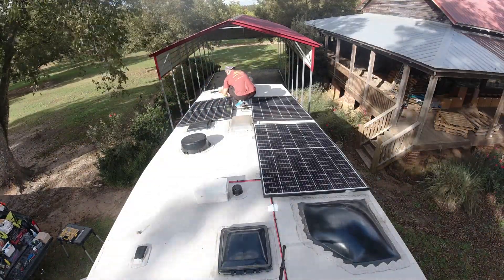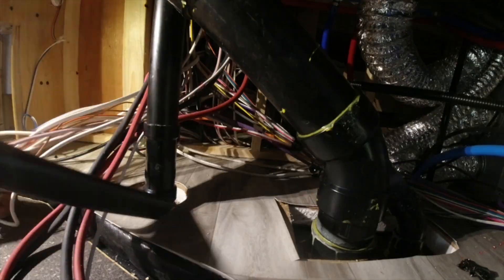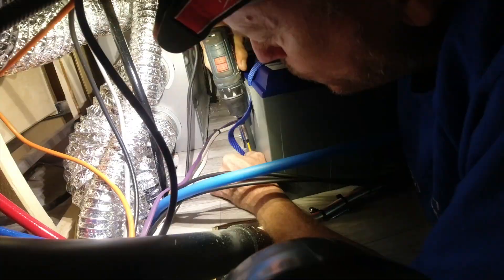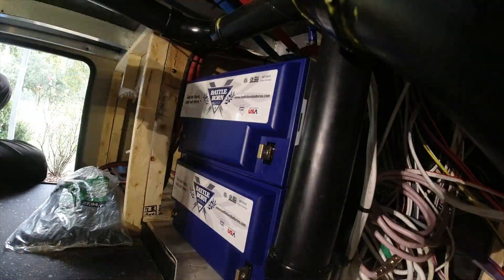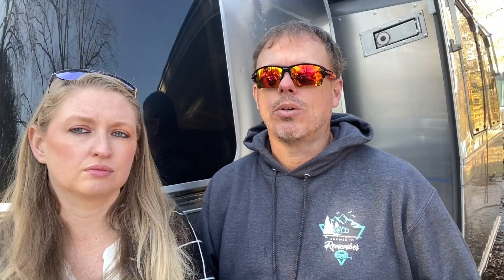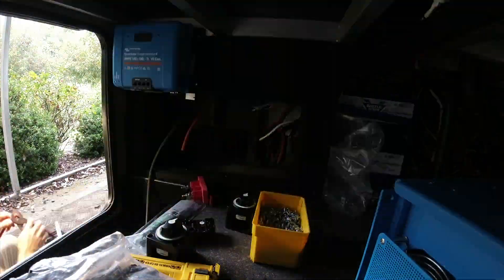Once we got the wiring tackled, I got inside and started the tearout before the rebuild — pulled all the steps out and designed the rebuild structure. Then I moved over to the plumbing side and cleaned a lot of that up. Because of the basement layout behind the wall, I had to split the battery bank into two sections, which meant there wasn't enough room to keep the MPPT in the same area as the Multi-Plus, switches, and fuses. After getting the batteries in place, I fastened the ducting down so it wasn't flopping around — that's a safety issue — making sure ducting is secured whenever a battery bank goes in.